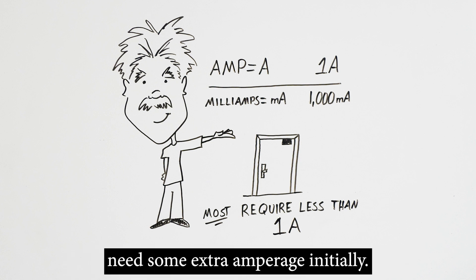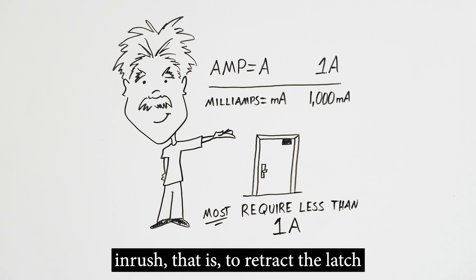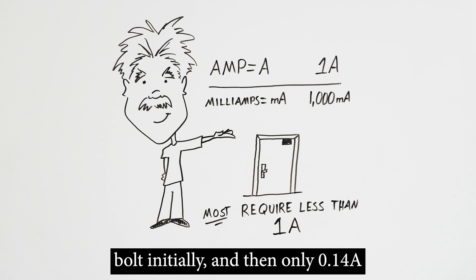The QEL device, for example, requires 1.4 amp inrush, that is, to retract the latch bolt initially, and then only 0.14 amps holding to keep the latch retracted.